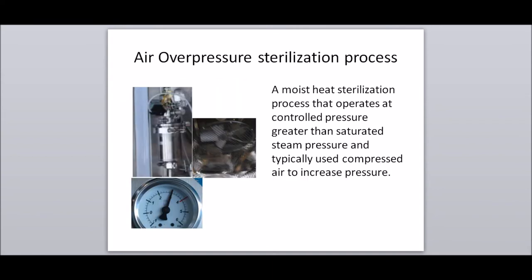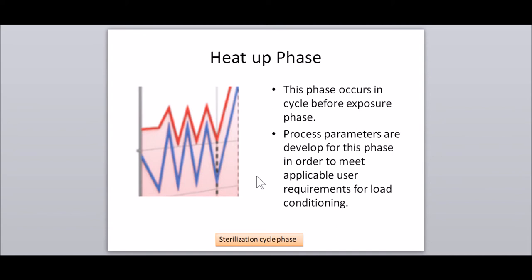Air over pressure sterilization process: a moist heat sterilization process that operates at a controlled pressure greater than saturated steam pressure, and typically uses compressed air to increase pressure. Heat up phase: this phase occurs in a cycle before the exposure phase. The process parameters are developed for this phase to meet applicable user requirements for load conditioning, such as air removal and preheating.